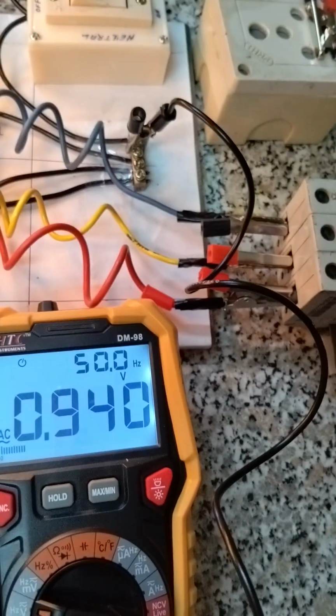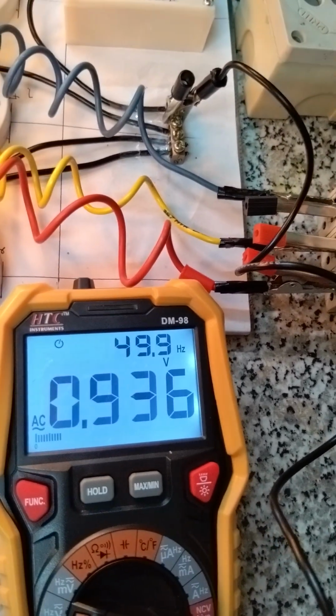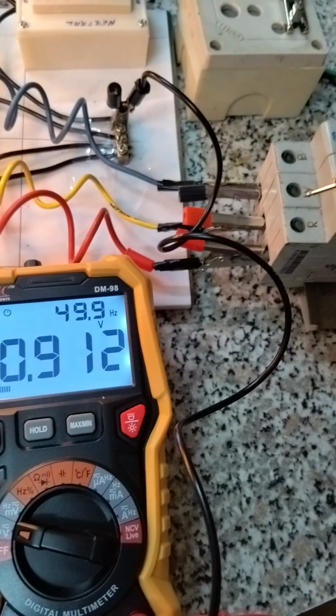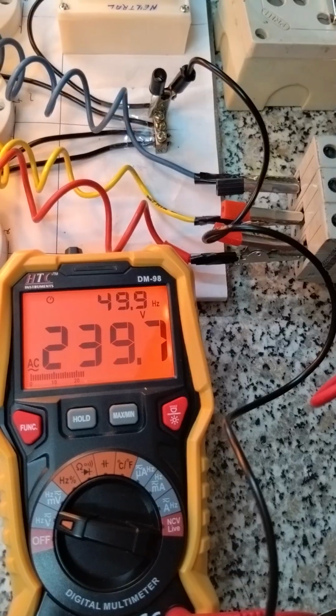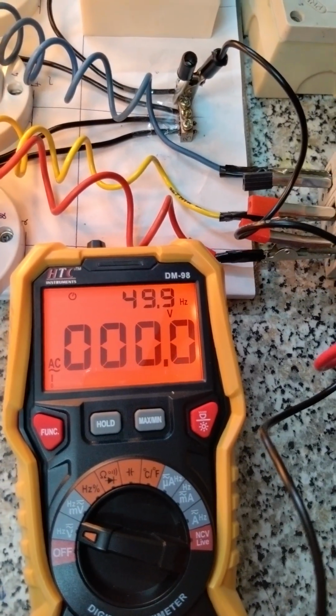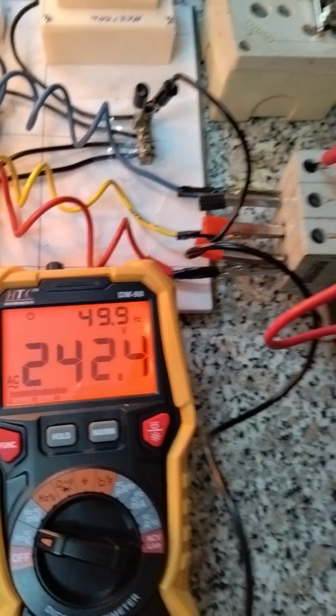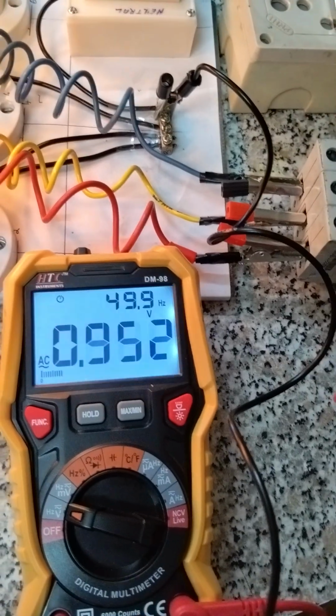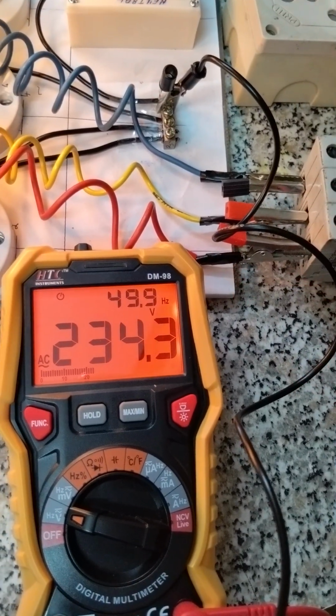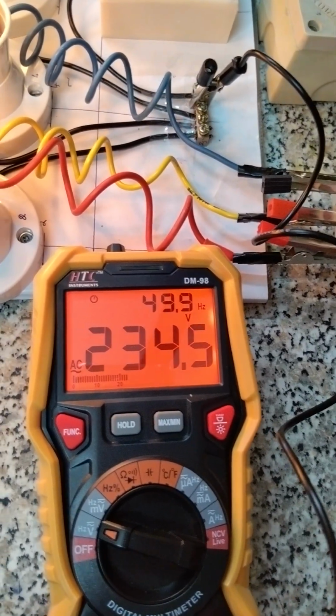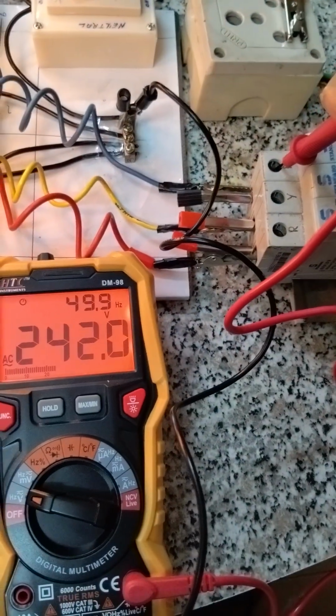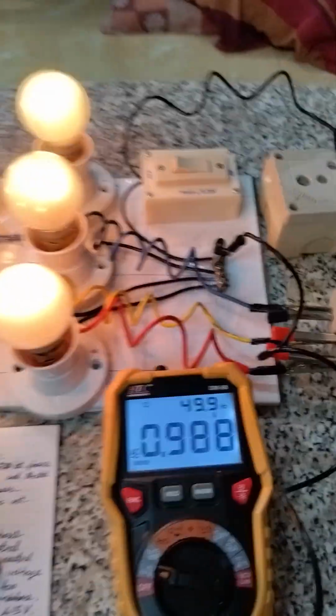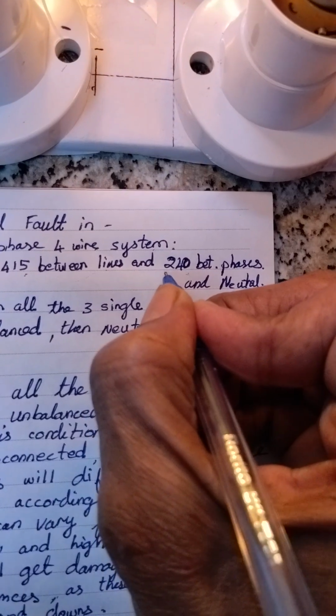We will check each phase and neutral. Already neutral I have connected. Please watch the reading. So 213, 240, 242, 242. Again I will show you. 236, 242, 242. So we have checked this parameter also. I will put a tick mark.